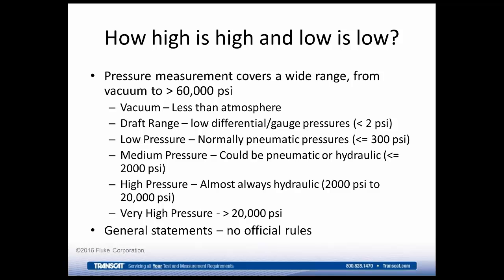Our product line can include measurement devices up to 60,000 or even 75,000 psi. Sometimes there's a need for higher, but it's a very rare case. As I said, there are no official rules on this. This is just a general statement to give a frame of reference. For some people who specialize in one particular range, they may consider everything else as being high pressure. For example, if all you do every day is work in the draft range, then even 300 psi is really high pressure for you.